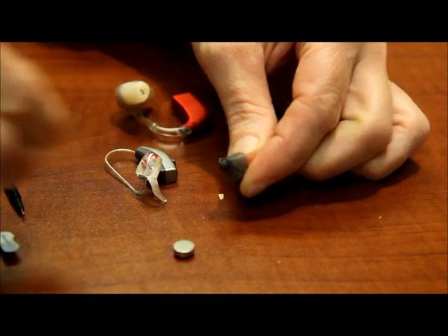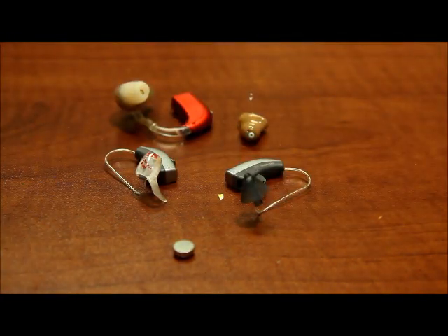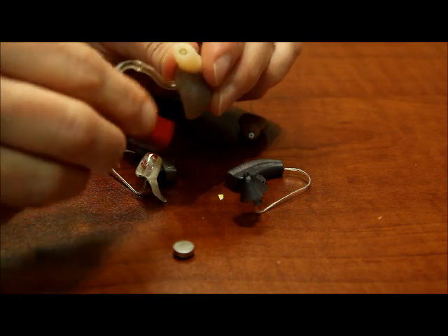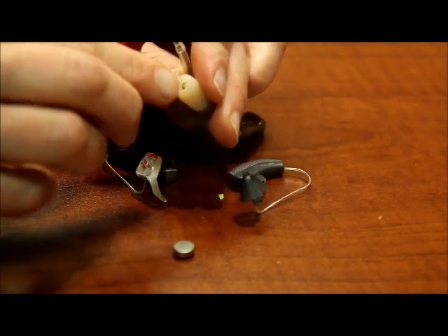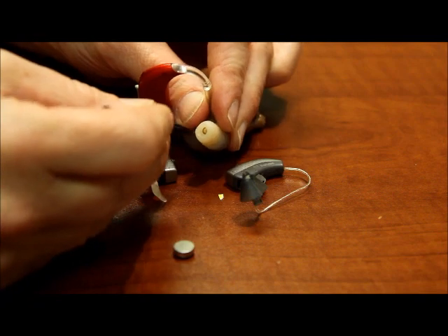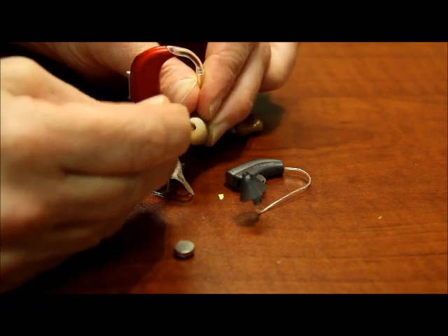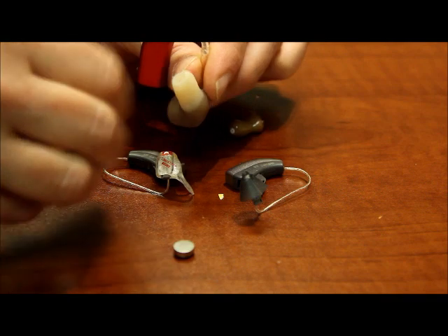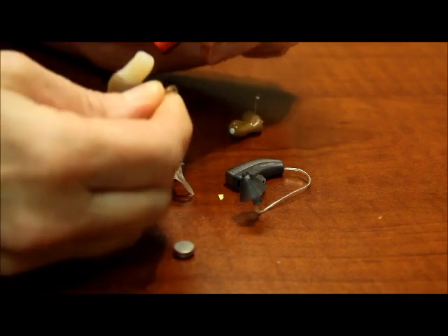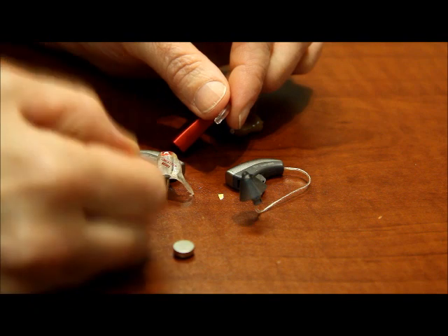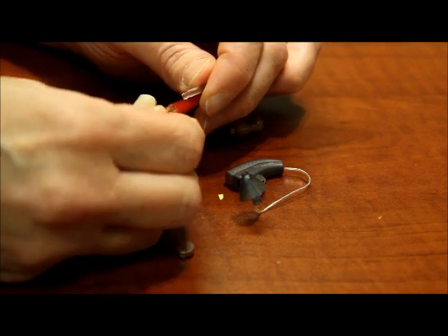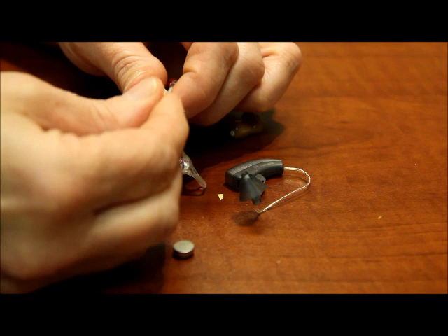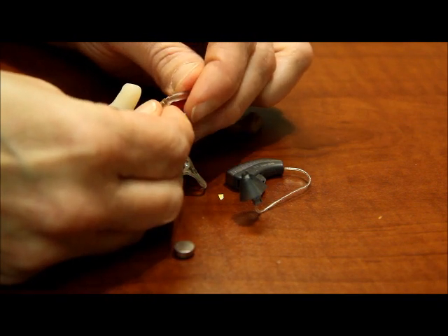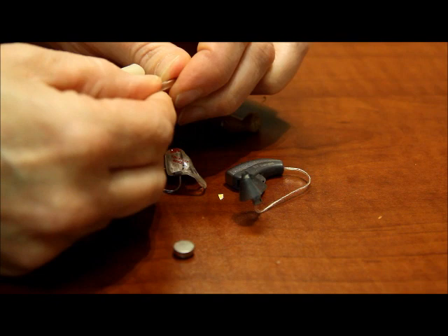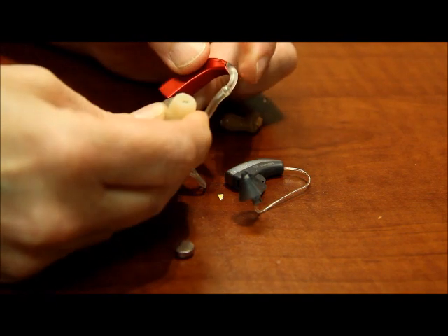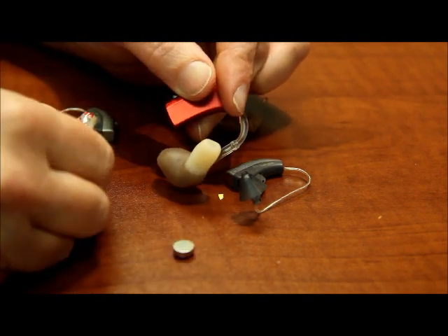Some other things to check on different styles of hearing aids would be on a BTE style hearing aid that uses an ear mold with a tube. Check the ear mold and the tubing to see if there are any obstructions. If you look at the end of the tubing, you can clean that out a little bit. That tubing can also get fluid in it. In that case, if you want, at home, you can blow out the tube if you have what's called an ear mold tubing blower. Most people don't have that. We can do it here in our office, but generally if your ear mold tubing has fluid in it, you want to get that cleaned out and replaced, and we can do that in our office.